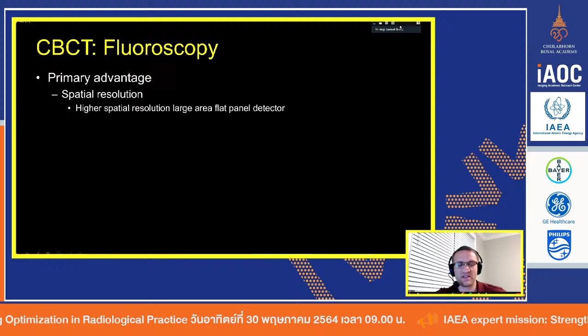The C-arm system has a better, higher spatial resolution. And it's because of the type of detector. It's a large, flat panel, really small detector elements, teeny, much smaller than the actual traditional CT scanner. And so you get really good spatial resolution with the C-arm CBCT systems. The primary limitation of these, however, is that they are slow. It takes about 8 seconds to do 3/4 of a spin around a body. So if you're doing, say, a CBCT for lung localization for needle advancement, it'll take 8 seconds. If you do it for the body, it'll take 8 seconds.